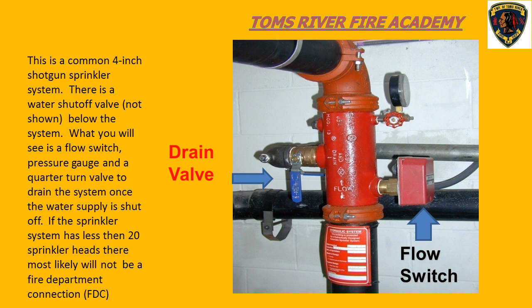This is a picture of a 4-inch shotgun wet system. We can see here we have a drain valve, we have a pressure gauge that tells us what the pressure is on the system, and we have a flow switch that goes back to the fire alarm system. One thing we don't see in the picture is a shut-off valve for the water supply. It's out of frame.